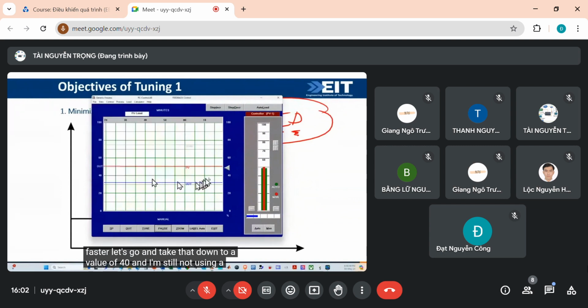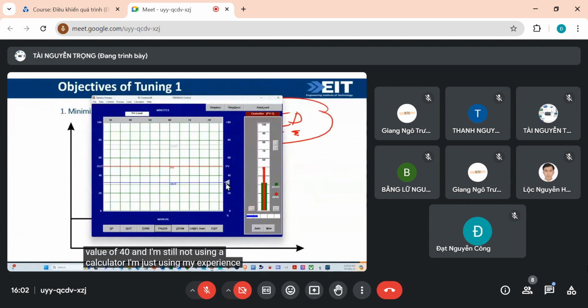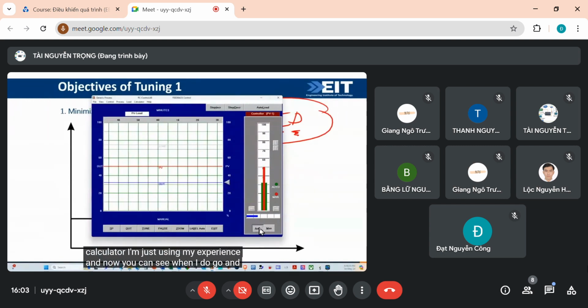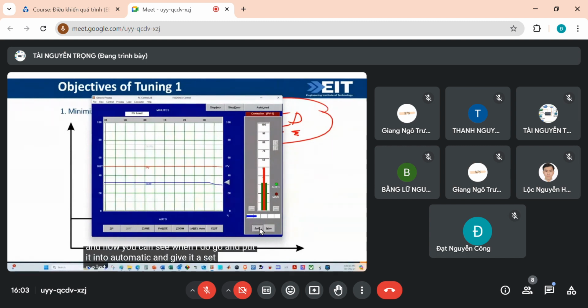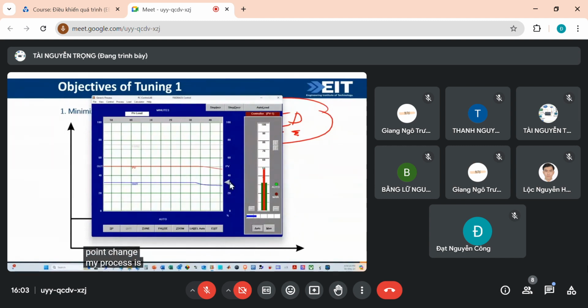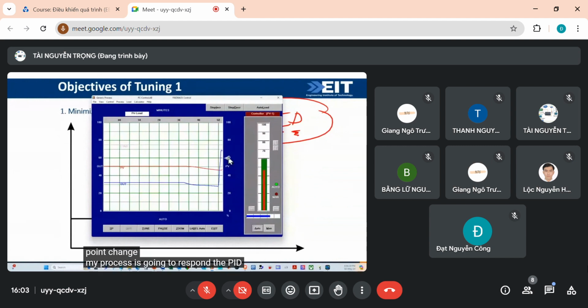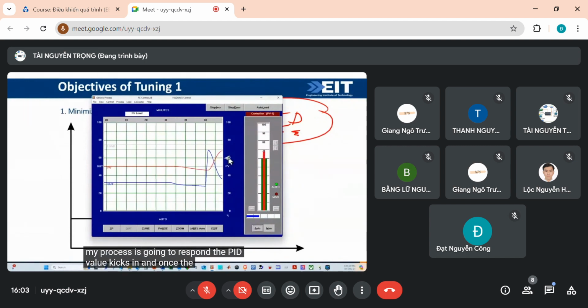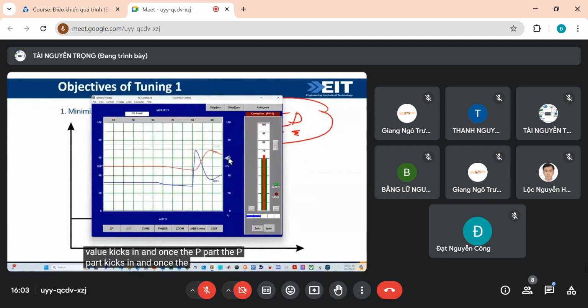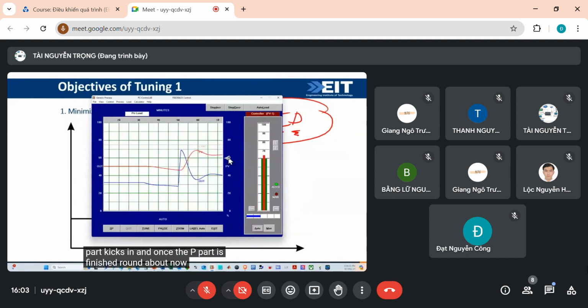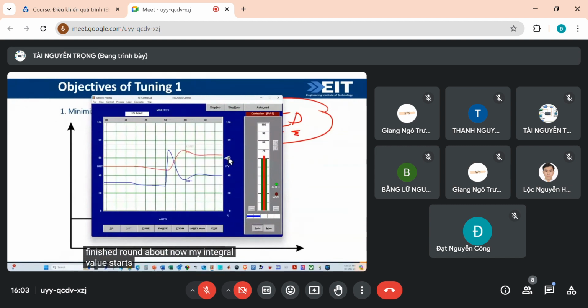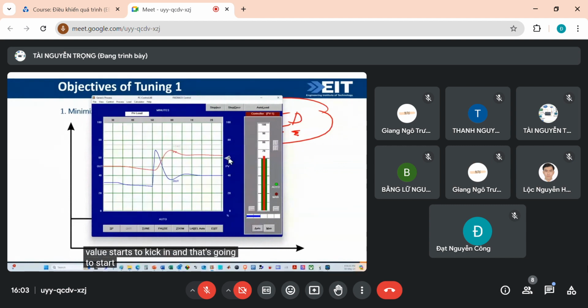And I'm still not using a calculator, just using my experience. Now you can see when I put it into automatic and give it a set point change, my process is going to respond. The PID value kicks in. And once the P part is finished, round about now, my integral value starts to kick in, and that's going to eliminate the offset.